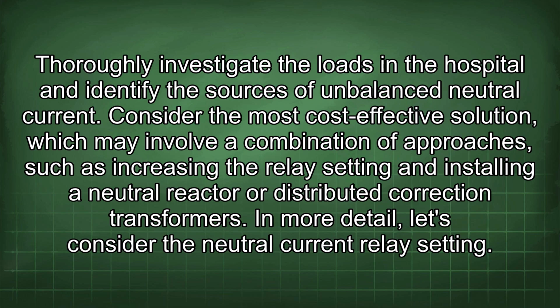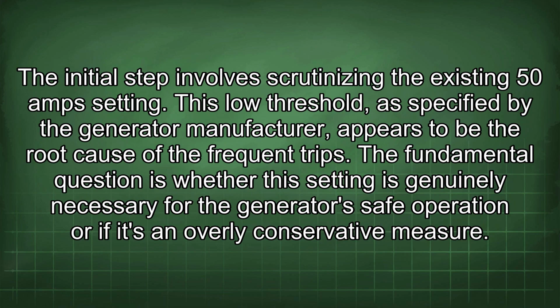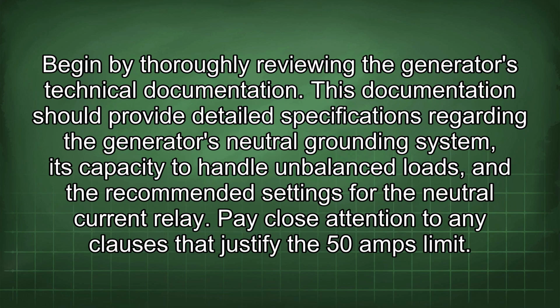In more detail, let's consider the neutral current relay setting. The initial step involves scrutinizing the existing 50 amp setting. This low threshold, as specified by the generator manufacturer, appears to be the root cause of the frequent trips. The fundamental question is whether this setting is genuinely necessary for the generator's safe operation or if it's an overly conservative measure. Begin by thoroughly reviewing the generator's technical documentation.